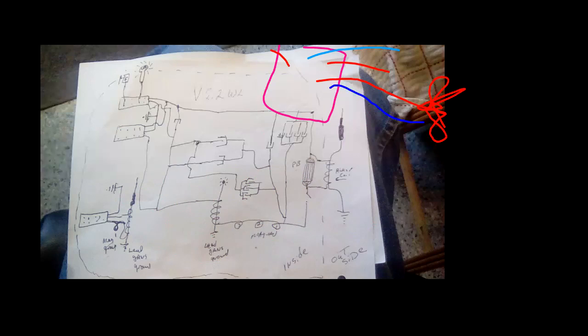That goes to a separate bus, a separate piece of, basically it's aluminum in most of them, but it's a place for everything to bind to. That neutral goes to ground. For the most part, the current is going to be traveling from the breaker box to ground. It's okay, no problems. Not only does your neutral bond to that bus in your breaker box, your ground wire, that middle wire in your appliances, which is green or bare copper, comes from your appliance. You see it go right down the middle, but it attaches to the same bus.